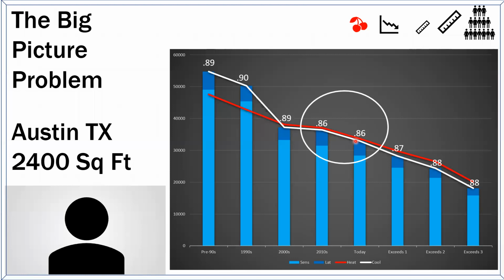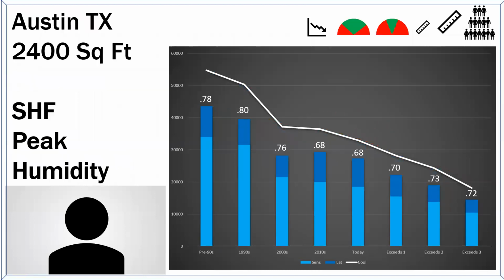But we're still improving the insulation, we're still improving the windows, we're still improving all this other stuff, which keeps shrinking that sensible load without shrinking the latent load. This is our unintended consequence. This is our problem. And it becomes a bigger problem if you start looking at loads on their peak humidity days.